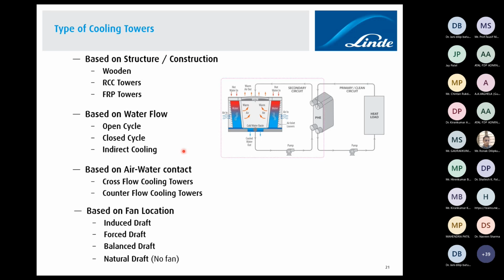Because what happens over a period of time, when a company is continuously expanding its facilities, you don't have sufficient space available around the cooling tower, which becomes a hurdle for cooling tower operation. So sometimes they install a long air duct and put the fans somewhere at a distance, so the fan will suck the air from a clearer area and push it into the cooling tower, because the cooling tower is either surrounded by a big building after expansion, or a large plant or some stack or a huge structure is obstructing the air movement.